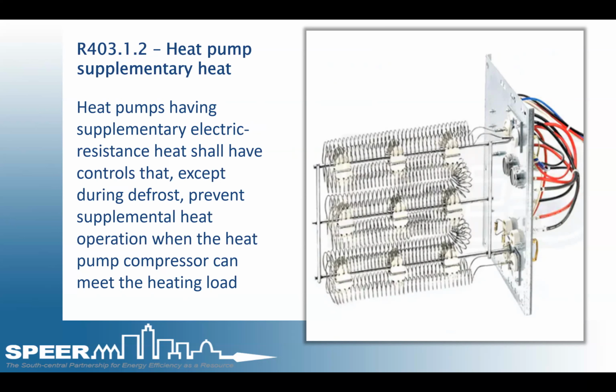We saw this a lot in Texas during Ice Storm Uri. Today's heat pumps can supply heat even down to temperatures close to freezing, or sometimes a little lower than that. And the stat in the unit should be programmed and set by the installer to not allow the heat strips to come on unless the compressor cannot meet the load. During Uri, most heat pumps had to use the electric resistance heat and put a large strain on an already struggling electrical grid.